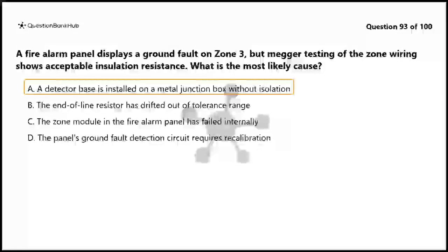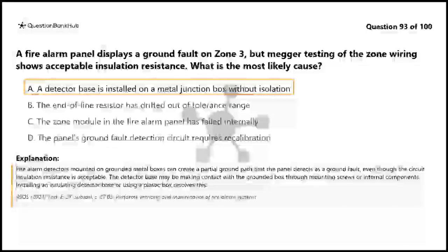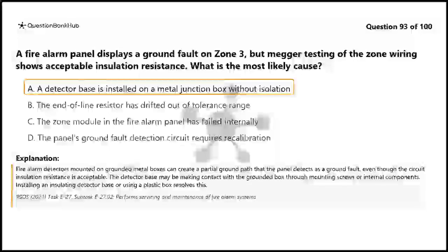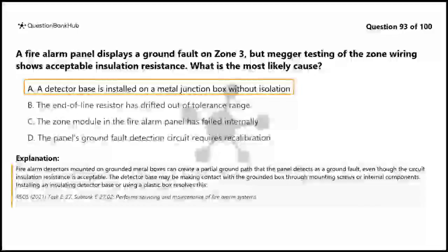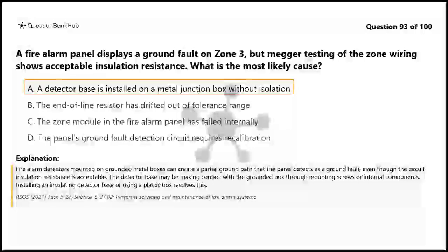The correct answer is A. A detector base is installed on a metal junction box without isolation. Fire alarm detectors mounted on grounded metal boxes can create a partial ground path that the panel detects as a ground fault, even though the circuit insulation resistance is acceptable. The detector base may be making contact with the grounded box through mounting screws or internal components. Installing an insulating detector base or using a plastic box resolves this.